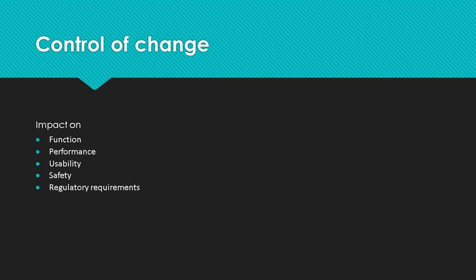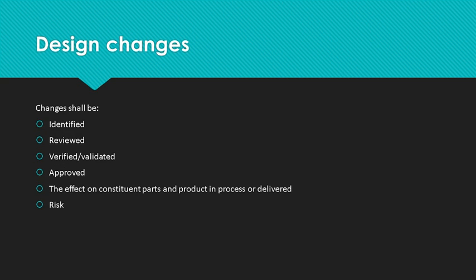Now, once the design is in production, the design team is still not finished. There must be procedures to control design change. The design team should be looking at the impact of the change on function, performance, usability, safety, and the regulatory requirements. And changes shall be identified, reviewed, verified, and validated, so you might have to repeat all of the original testing and validation, approved, and the effect on the constituent parts and products in process or delivered has to be evaluated and a disposition determined. And finally, the risk created by the change to the company has to be evaluated and addressed.